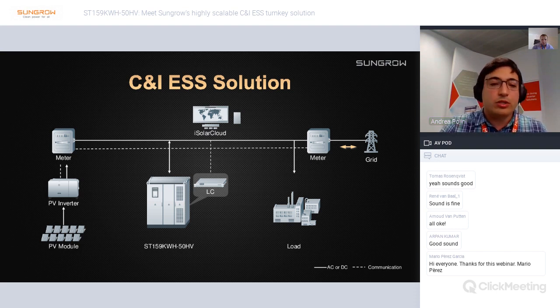On the left you see our customers' PV arrays connected to a PV inverter, and the production of this PV inverter is monitored by the first energy meter. The ESS is connected to the same AC grid as the rest of the loads on site, and the total site production and consumption is monitored by another energy meter on the right. The ESS local controller is connected to both energy meters and to the internet, providing easy access to our portal, iSolarCloud, for monitoring, and it also provides a direct connection to the client's EMS interface, the energy management system of the client.